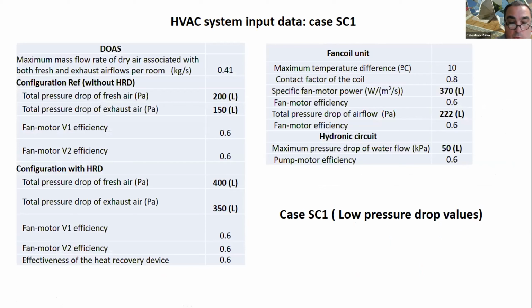Two scenarios were considered, scenario SC1 and scenario SC2. In scenario SC1, low pressure drop values in different airflows and in water flow were considered. When the heat recovery device is not used, we have considered 200 Pascal in the fresh air flow and 150 Pascal in the exhaust airflow in the dedicated outdoor air system. We have considered 400 Pascal and 350 Pascal in the dedicated outdoor air system, respectively, in fresh air and exhaust air when adopting a heat recovery device.